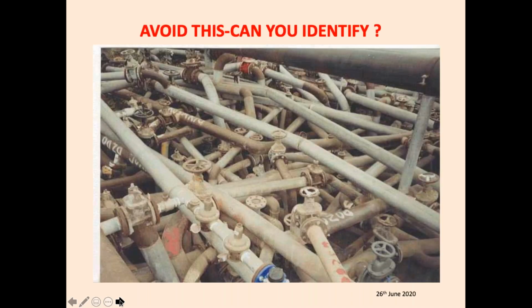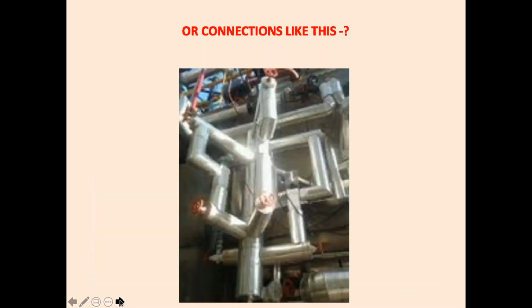So don't use piping like this. If you enter a new plant room, I have seen many times people call me and they say, "Sir, there is a problem in our plant, please have a look." When I go there, I have to trace out which pipe goes where because there is so much jumbling of piping. And I ask them, "Why did you do that?" They say, "Here also we have given a bypass, if this doesn't work then that will work, if that doesn't work then the other will work." So which is a very wrong practice. Don't jumble up the piping.